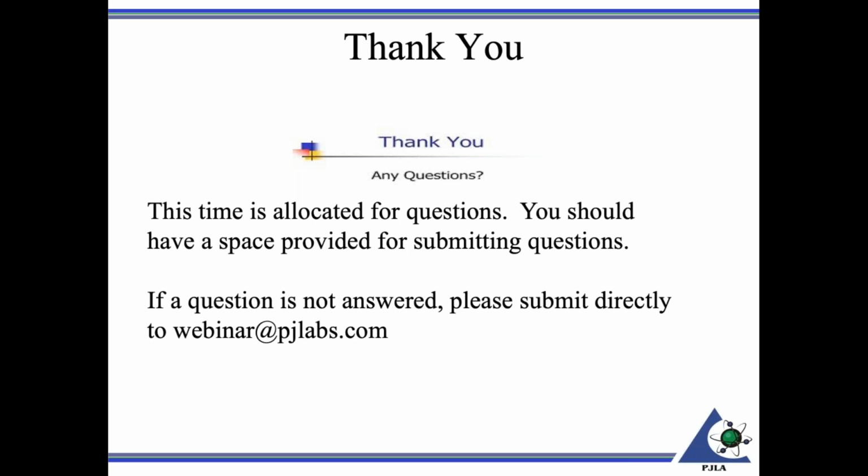Okay, so our first question was from earlier, so maybe this may have got answered, but the question was, what are the differences between a reference material certificate and a 17025 certificate? Oh, well, with a 17025 certificate, you're talking about things that would identify the material being tested, and any special environmental conditions that were part of testing if that would have had an effect. You normally would have the description of the test method, a description of the specimens, and the test results. It may or may not have uncertainty. It may be required that you indicate that something's in limits, out of limits, acceptable, not acceptable, a certain grade or whatever. And then there has to be an understanding of what that process is like, how uncertainty is handled and things of that nature, or what the decision rule is.